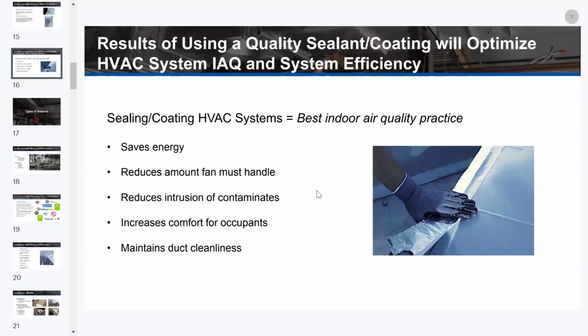So the results of using a quality sealant or a coating is going to optimize your system, indoor air quality, and your system efficiency. It's sealing properly and tightly on new construction, repairing and sealing air leaks on existing buildings. Sealing leaks in the system is one of the best IAQ practices, which saves cooling, heating, and fan energy. It reduces the load the fan must handle to deliver the same amount of air to the conditioned space. And once again, these all promote comfort for building occupants and healthy indoor air quality.